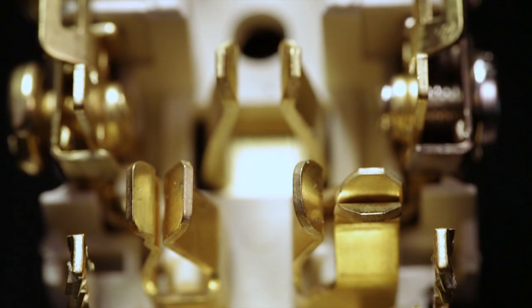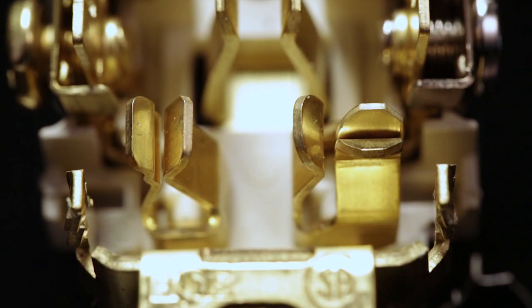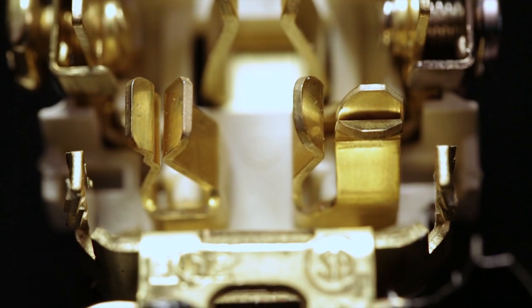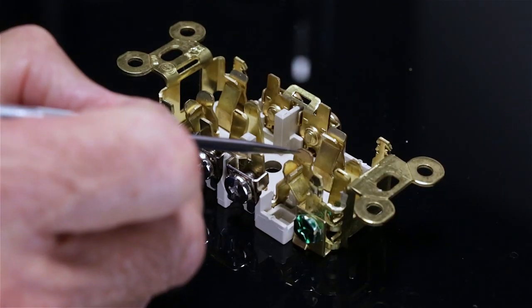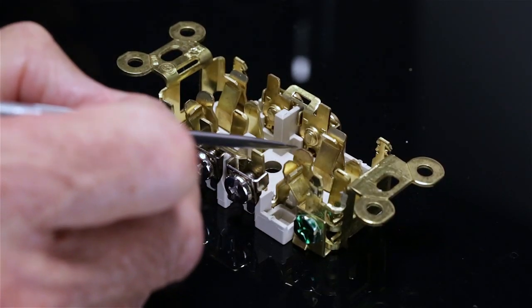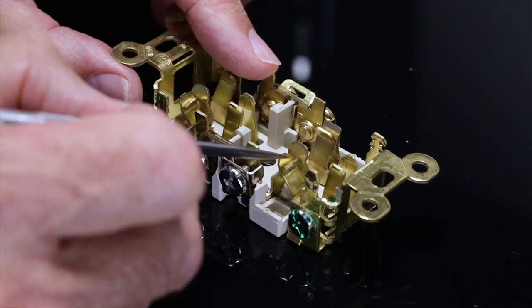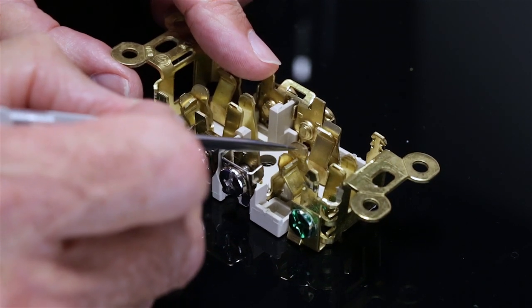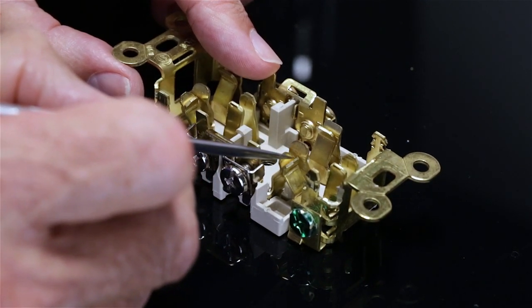Second, look at the size and quality of the brass and the size of the contacts. The blade of the power connector, if you'll see this point right here, actually contacts in three points. So the contact integrity of this type of contact is far superior to those commercial outlets we've just looked at.